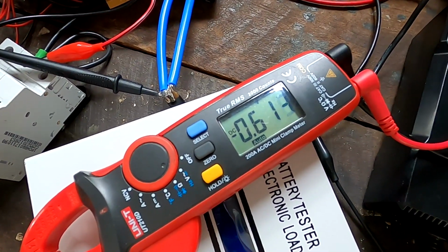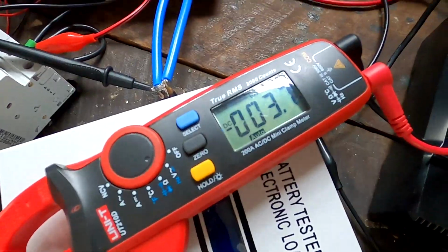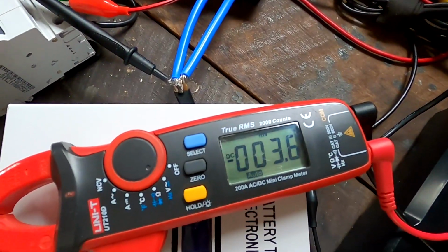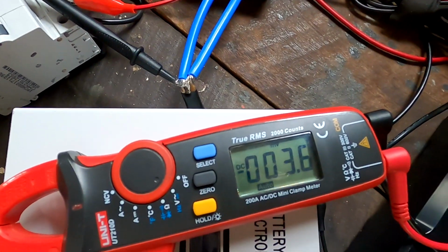Increasing further, at 1.5 amps it flips over. Around 1.5 to 1.6 amps it tips over, and then we've got full current going through the BMS, at only 3.5 millivolts. Guys, this is not normal, right? This cannot be normal, this is insane. There's something wrong with the BMS, unless it's a setting somewhere, but I wouldn't know what kind of setting that could be.